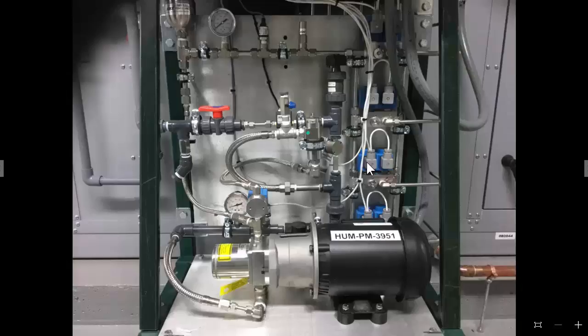So if the system starts up and this particular zone calls, power is applied to these two coils. The zone valve opens up and lets water through, and the dump valve closes, so there's no dump out to drain. That's normal operation. So let's say you call this zone to come on, and this opens up, but the dump side does not close. Water is going to come into the input of the valve and go straight through and out the bypass line to drain. That means it would not build pressure, so the system would go off on a low pressure alarm.